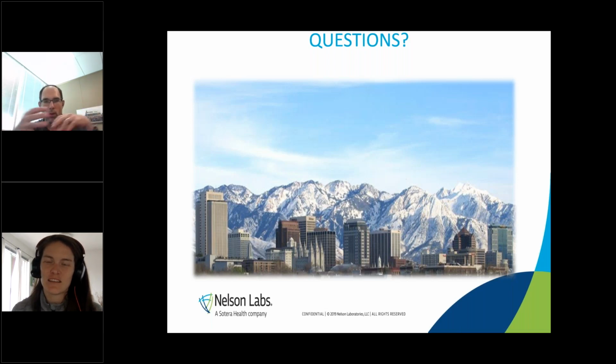So work with a biocomp lab and come up with a good test design to meet those endpoints that maybe aren't traditional biocomp. Traditional E&L may work for a lot of the endpoints, but definitely do a pre-sub. With CDER, they're more used to seeing that type of evaluation, but for CDRH, we want to talk with them beforehand. Gotcha. Yep. Always ask the questions first.